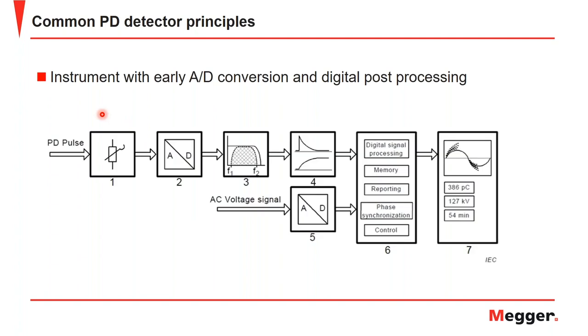Here we have the instrument with an early A to D, or analog to digital conversion, with post-digital processing. Here, again, your partial discharge pulse is fed into an attenuator that is fed to an analog digital converter, passed through a digital bandpass filter, then through a numeric integrator, and then your AC voltage source signal has an analog to digital converter, then your digital post-processing through your acquisition unit, and then finally your evaluation and visualization unit. And this follows the idea of the 60270 so-called quasi-integration, but instead of using a low-pass filter, F2 on the filter block here, 3, takes care of the integration. So the numerical integration is sometimes not necessary.